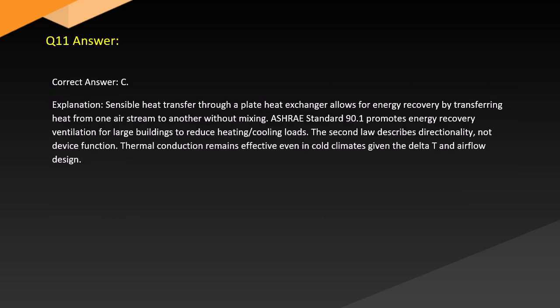Answer. Correct answer: C. Explanation. Sensible heat transfer through a plate heat exchanger allows for energy recovery by transferring heat from one airstream to another without mixing. ASHRAE Standard 90.1 promotes energy recovery ventilation for large buildings to reduce heating and cooling loads. The second law describes directionality, not device function. Thermal conduction remains effective even in cold climates given the delta T and airflow design.